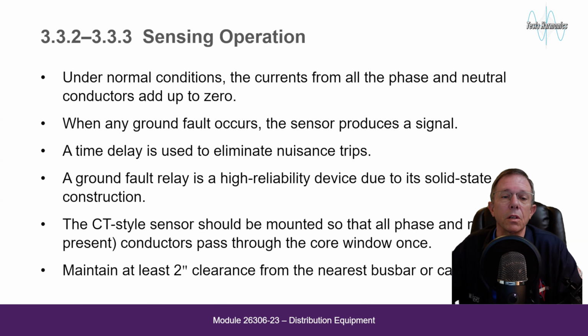A time delay is used to eliminate nuisance trips, and a ground fault relay is a high reliability device due to its solid-state construction. The CT-style sensor should be mounted so that all phase and neutral, if present, conductors pass through the core window once. Maintain at least 2 inches of clearance from the nearest bus bar or cable.